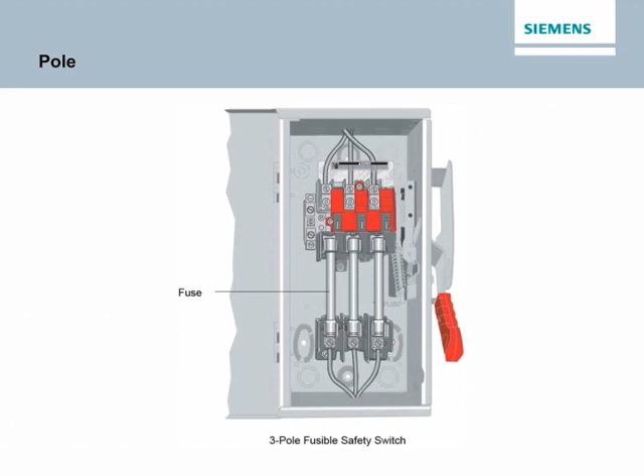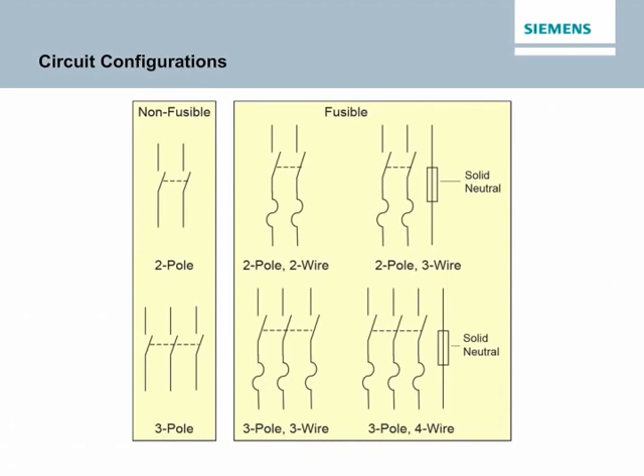Circuit configuration diagrams for 2- and 3-pole safety switches are shown in the accompanying illustration. As the illustration shows, safety switches may be fusible, non-fusible, or fusible with a solid neutral. Siemens safety switches are available in all the configurations shown in the accompanying illustration, as well as additional configurations. For example, Siemens heavy-duty fusible and non-fusible safety switches are also available with 4 or 6 poles.